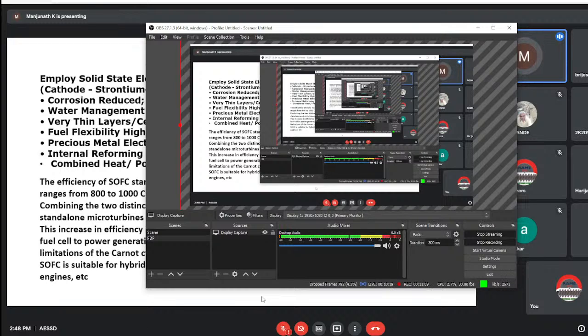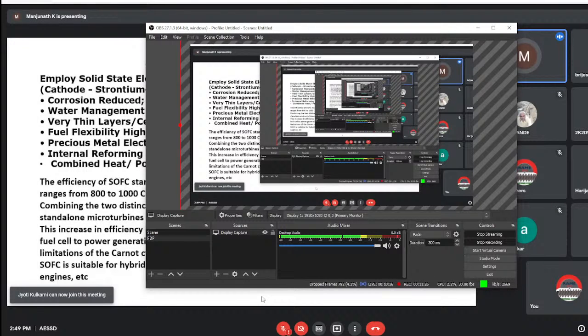So this is an advantage to go for the hybrid system. Combining two distinct systems increases the efficiency compared to standalone gas turbines, which will be having 25 to 30%. So we can increase it by combining with solid oxide fuel cells to 65%.